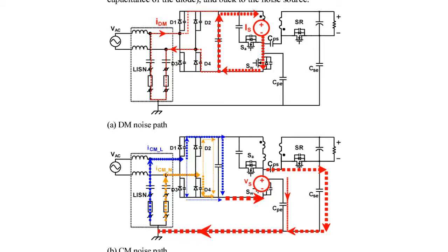Electronic equipment is 10 to 100 times more sensitive to common mode noise than to normal mode noise. Conventional power transformers and isolation transformers will not block normal mode noise impulses, but if the secondaries of these transformers have the neutral bonded to ground, they serve to convert common mode noise to normal mode noise.